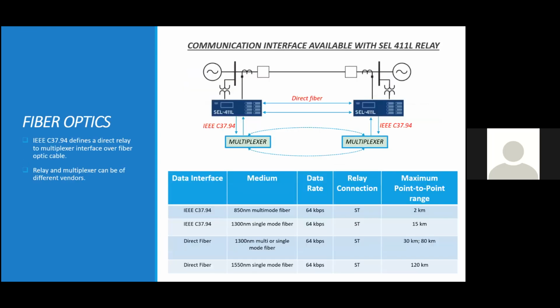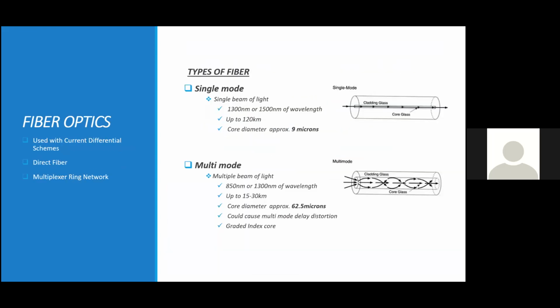And so fiber is generally used with current differential schemes. Current differential schemes are used for relatively shorter lines, and we could also use this as a direct fiber connection between the two terminals of the transmission line. And we could also use a multiplexer ring network of fiber.